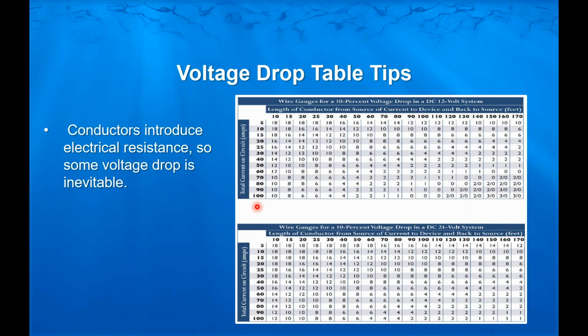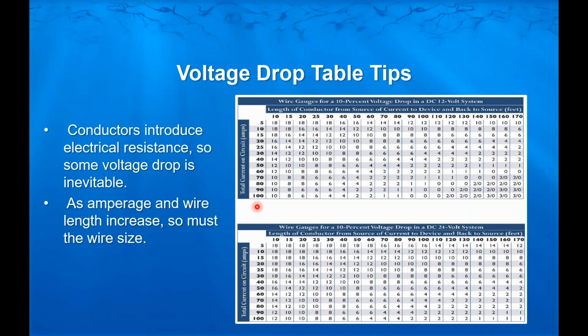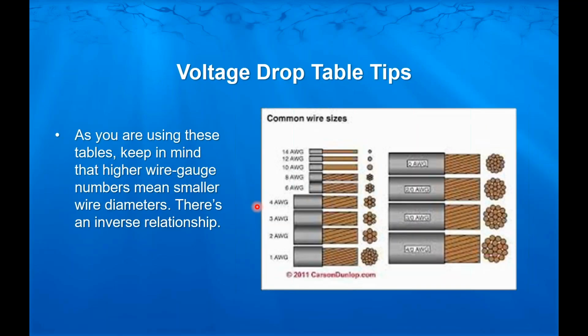Conductors introduce electrical resistance, so some voltage drop is inevitable. We can't have zero voltage drop, but 3% is pretty close. The general rule is, as amperage and wire length increase, so must the wire size. As you're using these tables, keep in mind, if you're not terribly familiar with wire gauges, the higher the wire gauge number, the smaller the diameter. There's an inverse relationship. So we can see our 14 gauge, high number, very small cable. 1 gauge, low number, very big cable.